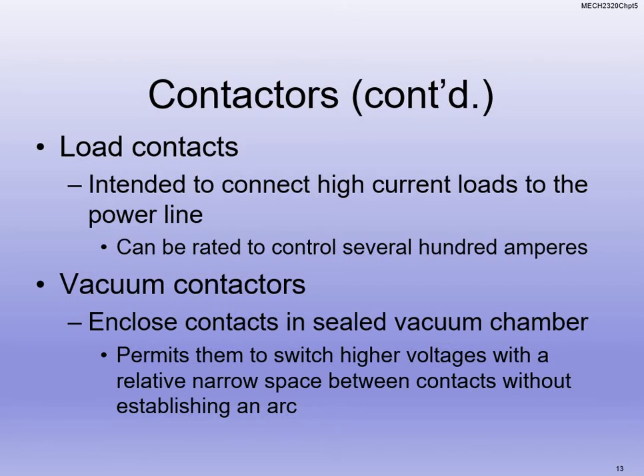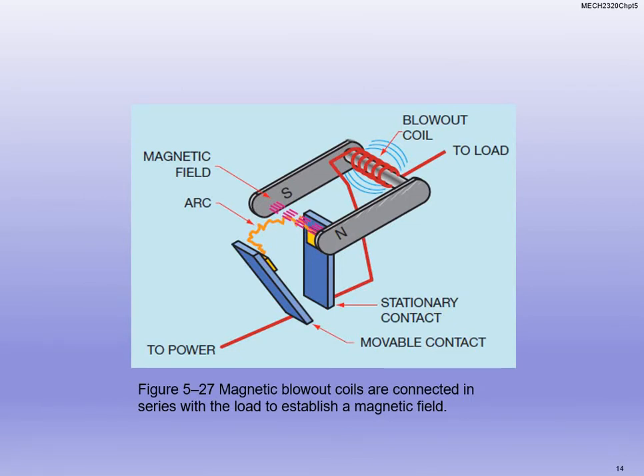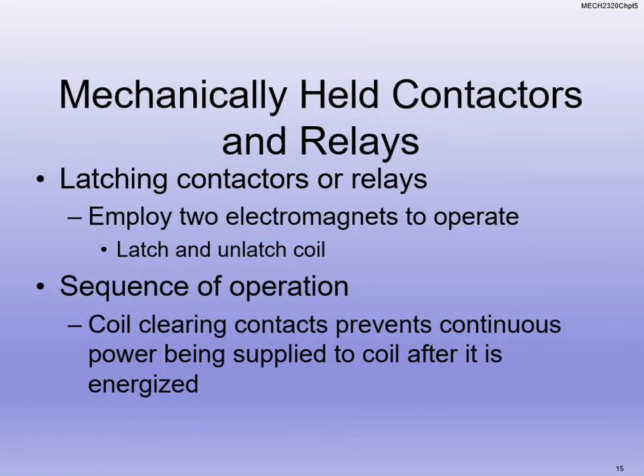We can also use vacuum contactors for special situations where we need to switch higher voltages and narrow the space between them without arcing as much — there's really nothing in a vacuum for it to arc on. We can also use magnetic blowout coils to help establish a magnetic field as current goes through it, giving off a magnetic field to open, close, or blast those contacts.